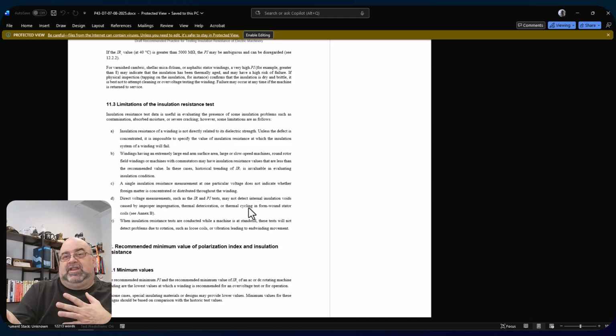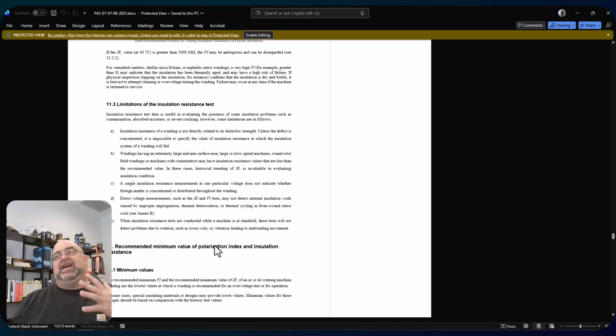I didn't put this in there. I vote on it, and I'm part of the discussion, but this section was somebody else. When insulation resistance tests are conducted while a machine is at standstill, these tests will not detect problems due to rotation, such as loose coil. Basically, it's saying you can't tell winding issues or other conditions with insulation resistance.